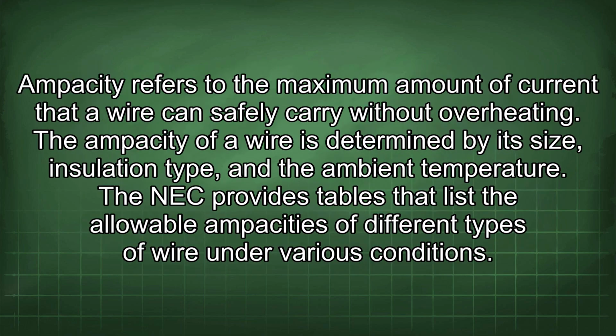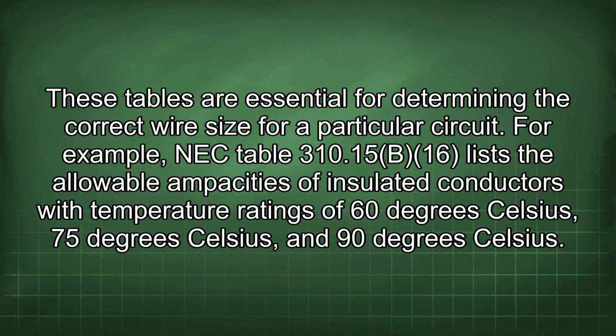Ampacity refers to the maximum amount of current that a wire can safely carry without overheating. The ampacity of a wire is determined by its size, insulation type, and the ambient temperature. The NEC provides tables that list the allowable ampacities of different types of wire under various conditions. These tables are essential for determining the correct wire size for a particular circuit.